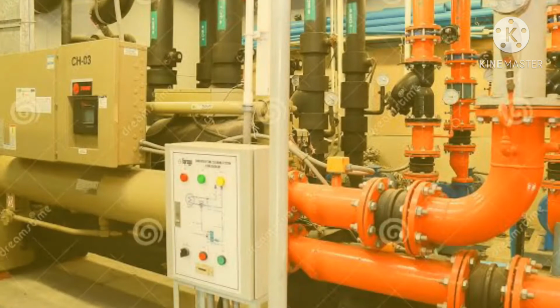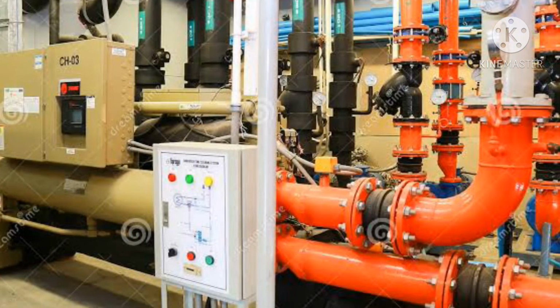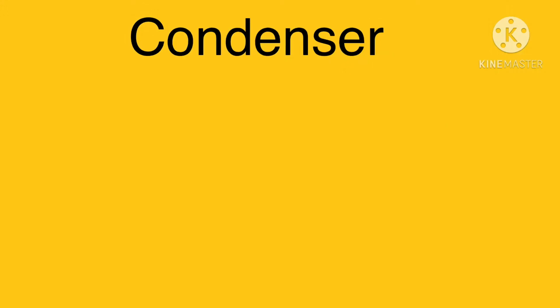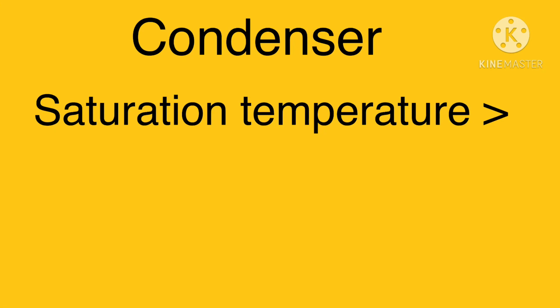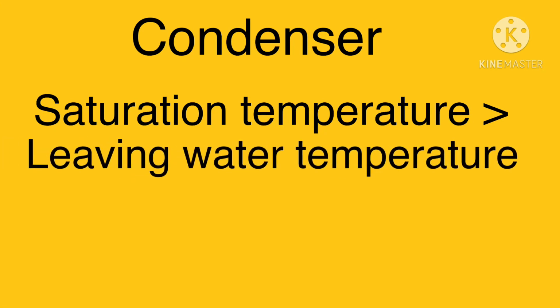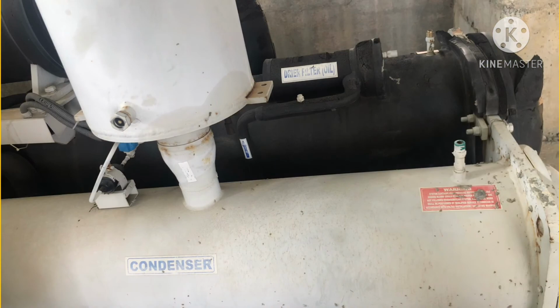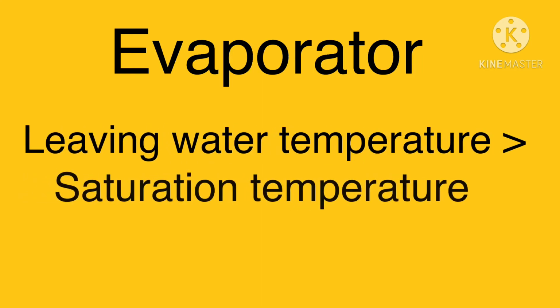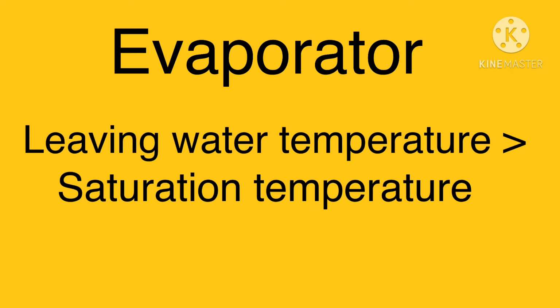Here you may get a little confusion about the formulas of condenser approach and evaporator approach. In the case of condenser approach, saturation temperature is greater than leaving water temperature. That's why in the formula, condenser approach is equal to saturation temperature minus leaving water temperature. Why? Because saturation temperature is higher in the condenser. In the case of the evaporator, leaving water temperature is greater than the saturation temperature. That's why in the formula of evaporator approach, it is leaving water temperature minus saturation temperature. Why? Because leaving water temperature is higher.